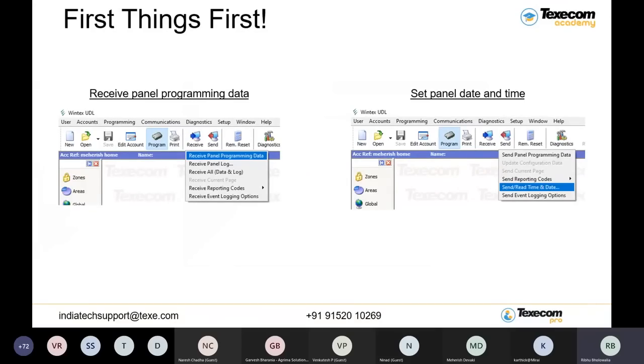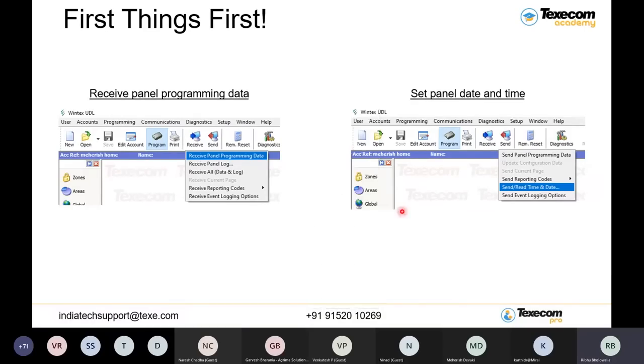So be very careful while using the Wintex software, especially when you have wireless sensors enrolled. If you have not done the receive panel programming data when you first connected, there may be a chance that you lose all your wireless programming, and you have to start over again.